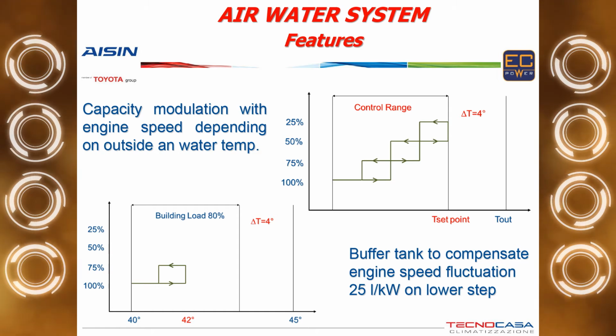The air-water system modulates based on the return temperature. So once the setting point is selected, and once the modulation range is selected, what we can do is reduce the speed of the engine. So it's not exactly a VRV system when it's air-to-water. It's more like a step-by-step, and we have 4 steps of modulation. So this means that if the building load is 80%, we will work for some time at 100% and for some time at 75%. So to avoid the engine changing speed very frequently, we have to foresee a buffer tank for the technical water.